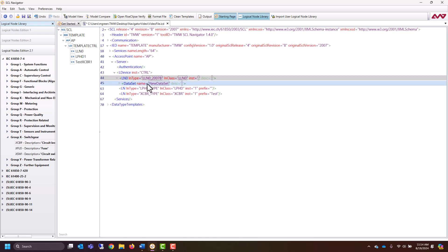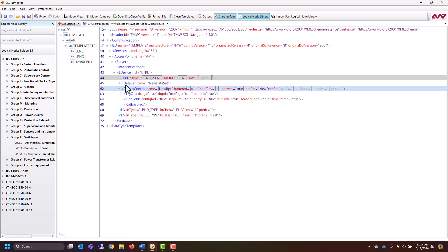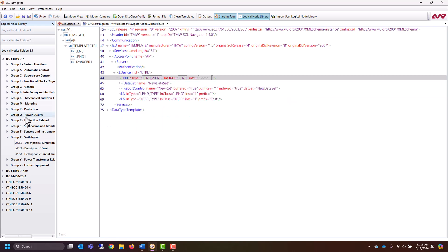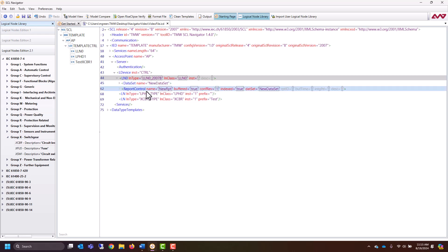Now inside of the LLN0, we see we have that new dataset. Once we have a dataset, we can do things like adding a report control block. So you right-click, Add, and let's do a buffered report control block. Let's go ahead and select the new dataset — that will allow us to have access to the dataset I just configured. Now we have added a new logical node to our template ICD, the data attributes within it such as the breaker position have been added to a dataset called 'new dataset', and we've created a report control block called 'new report control block' using that dataset.